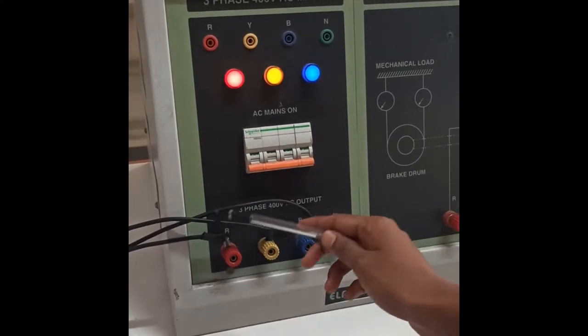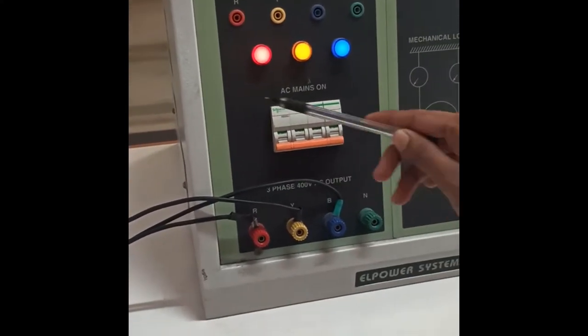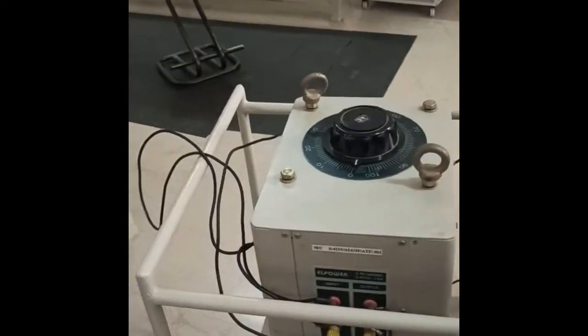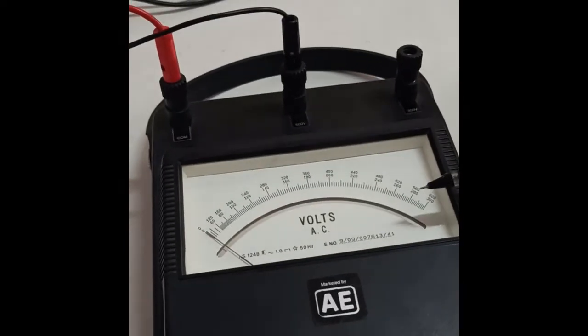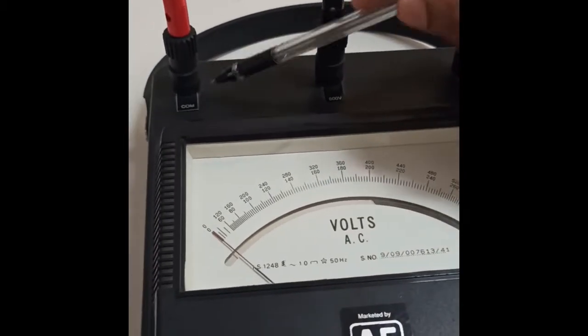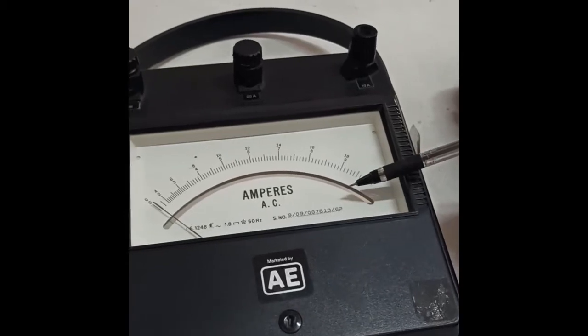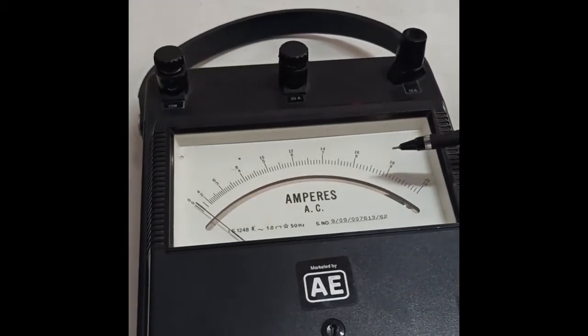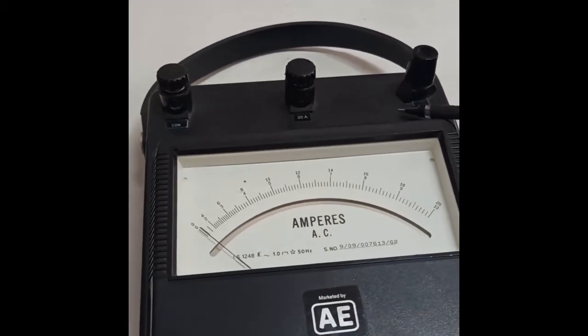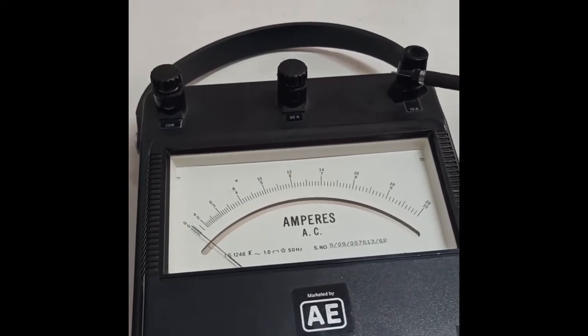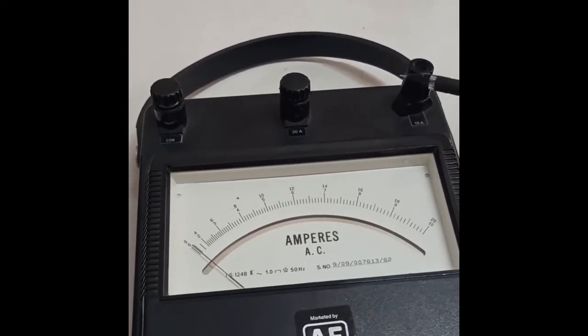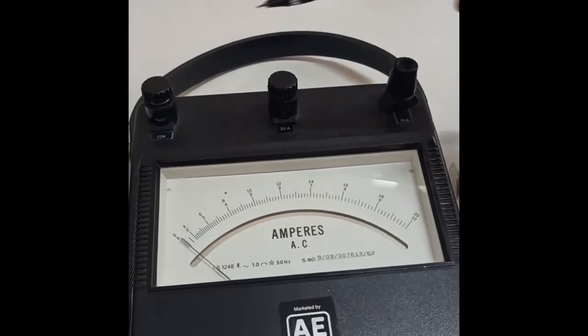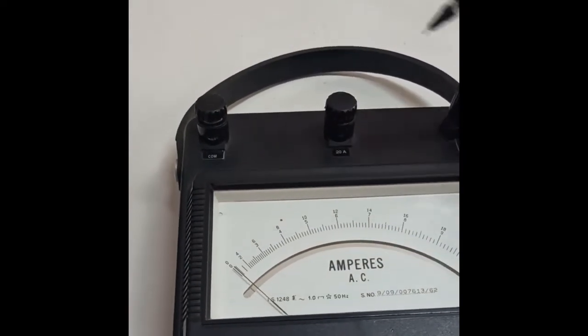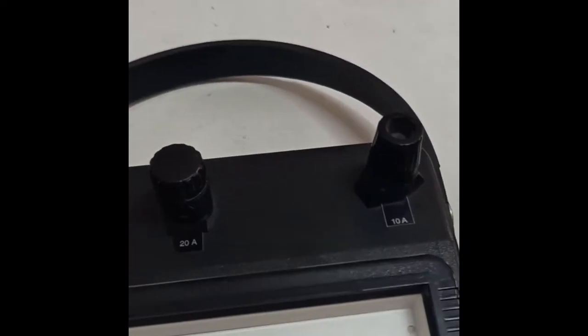For this experiment we need a three-phase supply. Then we require a three-phase auto transformer and one voltmeter to read the line voltage, of range 0 to 600 volts. Then we need one ammeter to measure the line current. Depending upon the machine rating, we have to select the range of the ammeter. So here the machine on which we are conducting the experiment has a rated current of 7.5 amperes. So we will choose the ammeter range to be 0 to 10 amps.